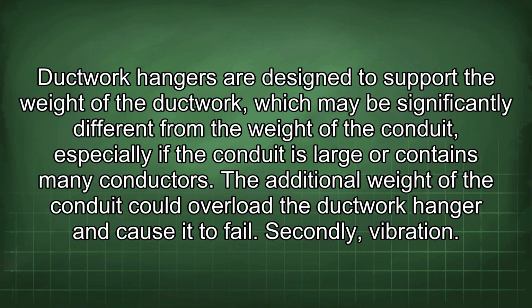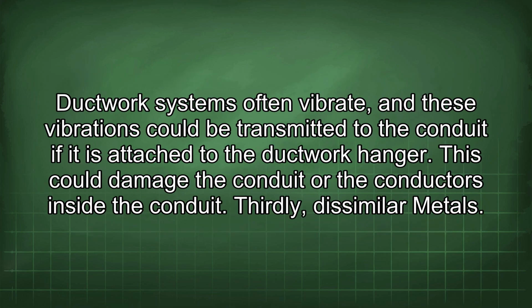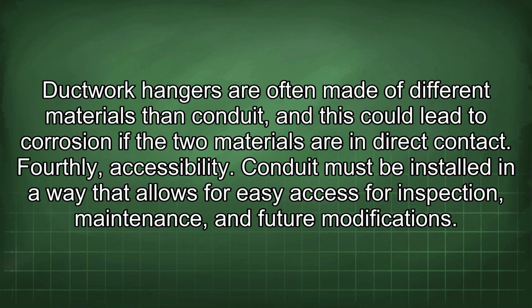Secondly, vibration. Ductwork systems often vibrate, and these vibrations could be transmitted to the conduit if it is attached to the ductwork hanger. This could damage the conduit or the conductors inside the conduit. Thirdly, dissimilar metals. Ductwork hangers are often made of different materials than conduit, and this could lead to corrosion if the two materials are in direct contact.